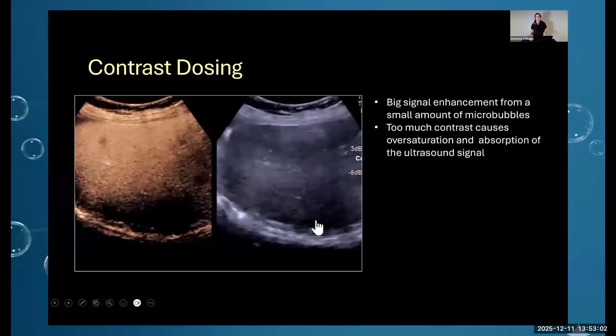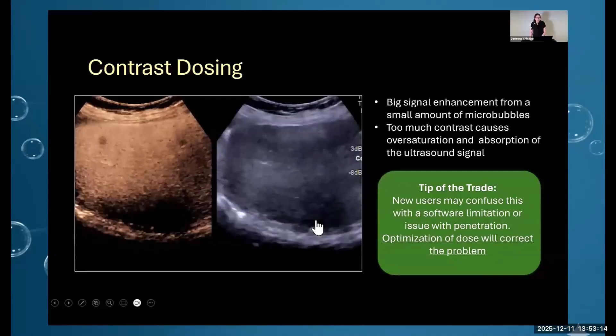Tips of the trade: new users may confuse this with a software limitation or issue with penetration. Optimization of dose will correct the problem. Focus. So this is a bit different than grayscale imaging as well. You want your focus placed at or below the structure of interest. Focus set at the incorrect depths create differences in penetration and bubble uniformity between the near and the far field.